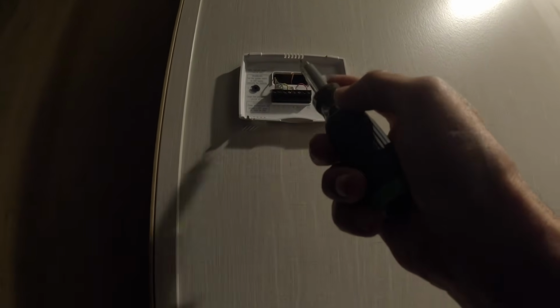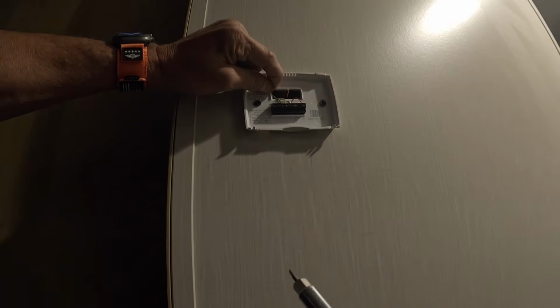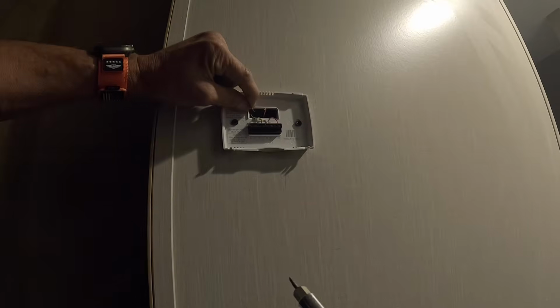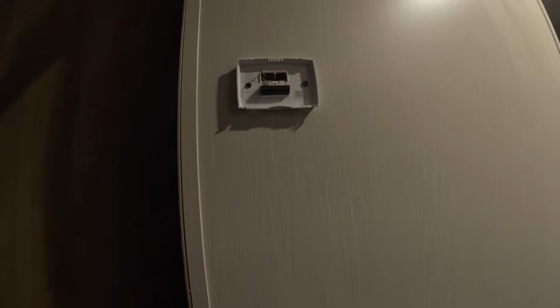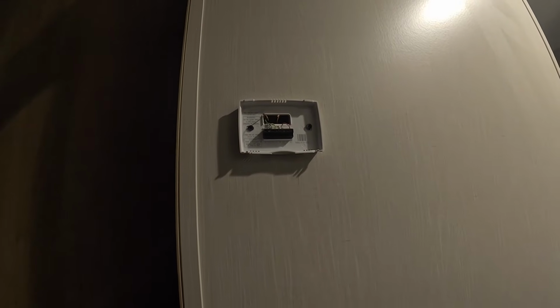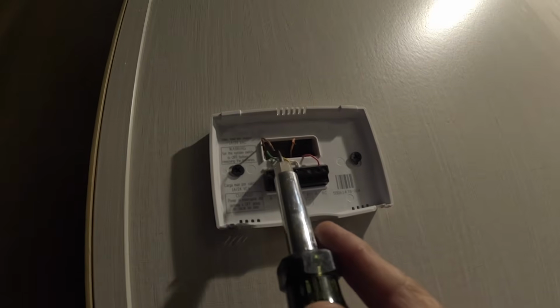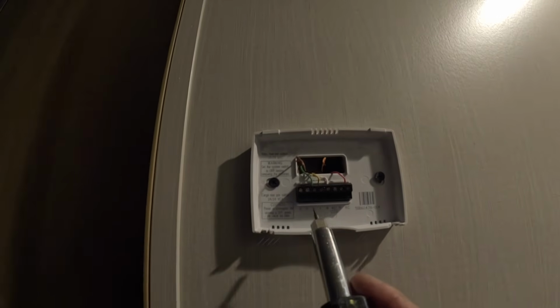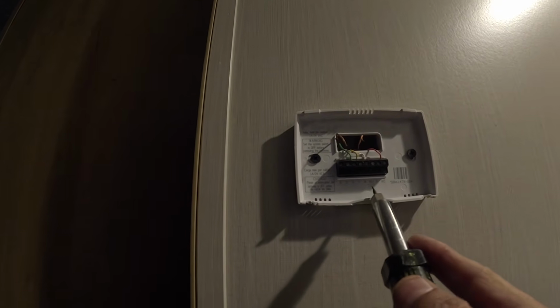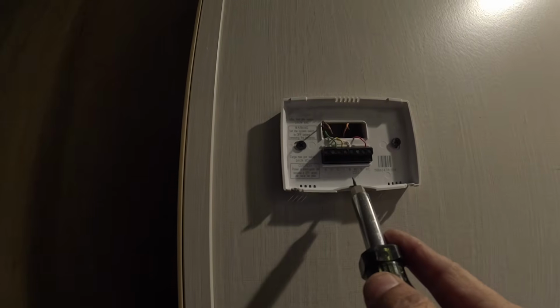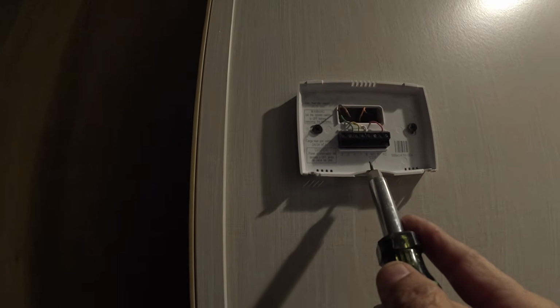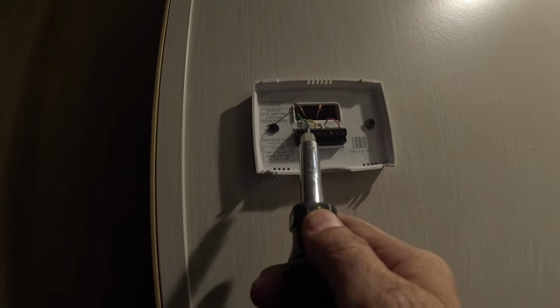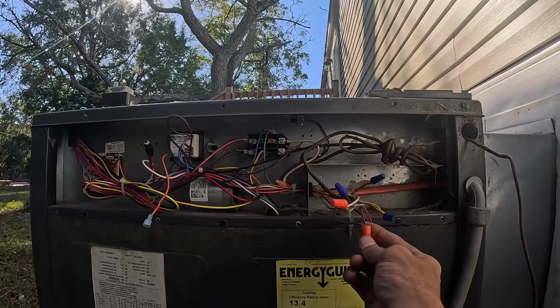All right, we got orange for reversing valve, red, white, yellow, green, and... all right, I'm a little bit confused. They got brown on B, orange on O, green, yellow. This thermostat doesn't have a common, but they got brown hooked up on B. Okay, out here, brown is hooked up to blue, which is my common. So brown is common.